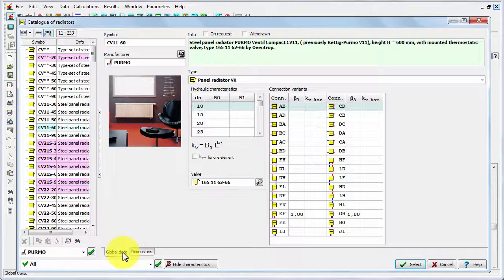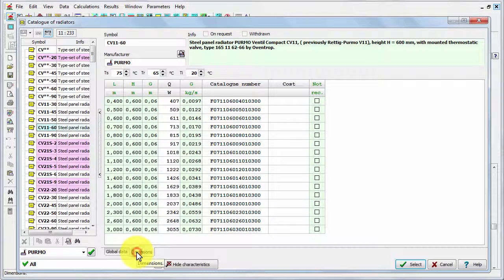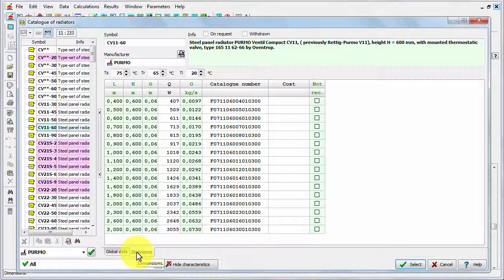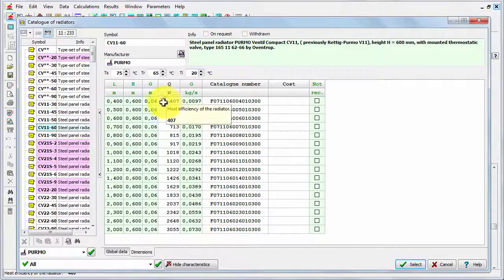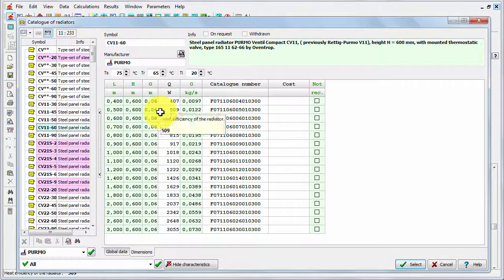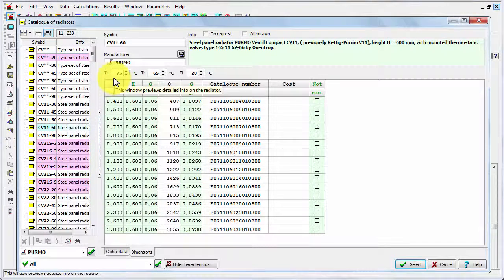It means that the height of radiator is 60 and it's got just one panel. If we change the type tab for the dimensions, then you can see the available dimensions. In this case, these are the possible lengths of the radiator, and you can also see the output of these radiators for the specific temperature.